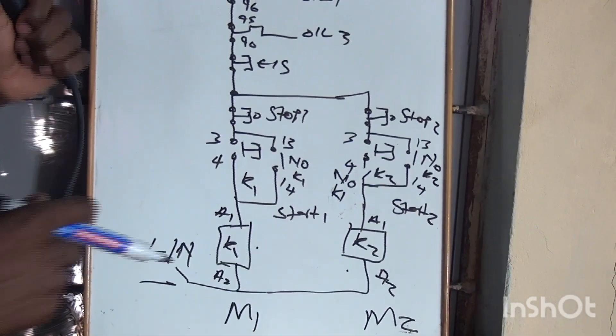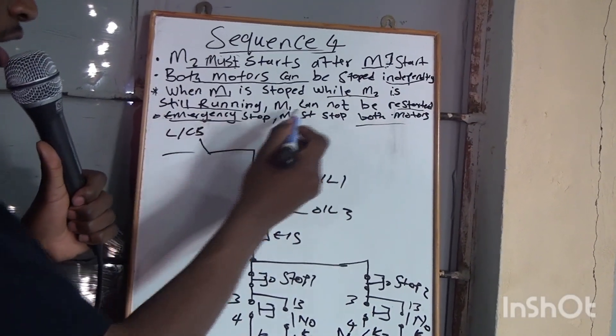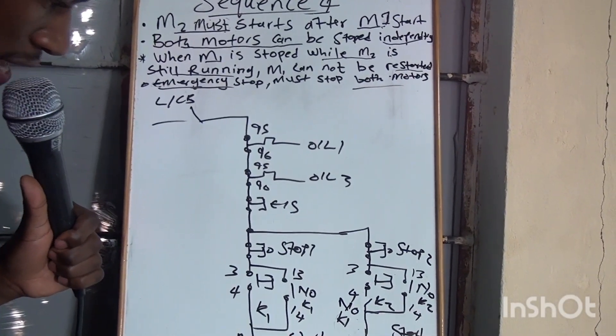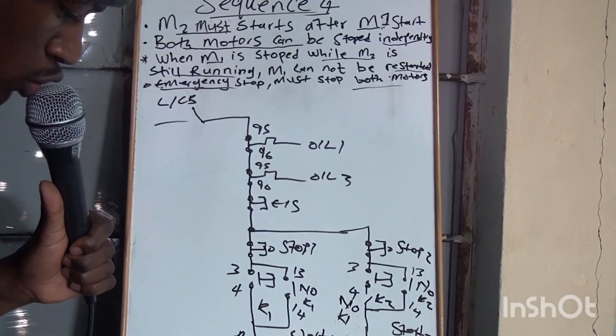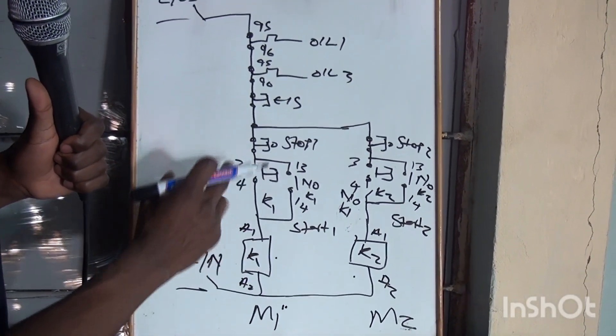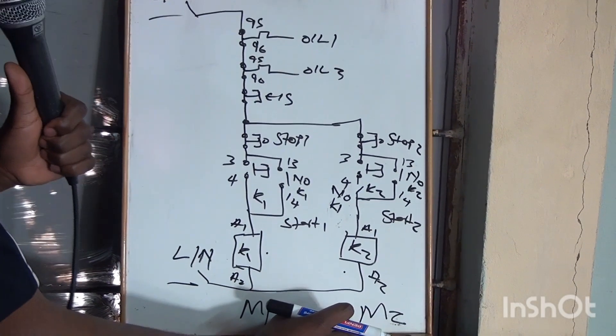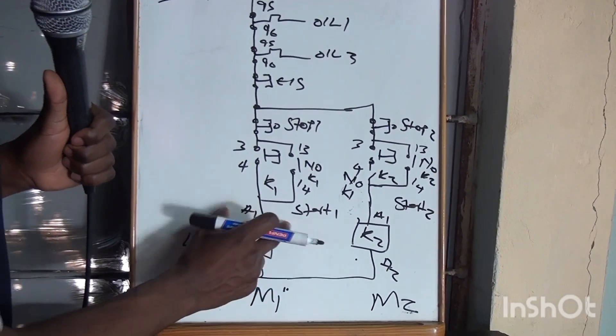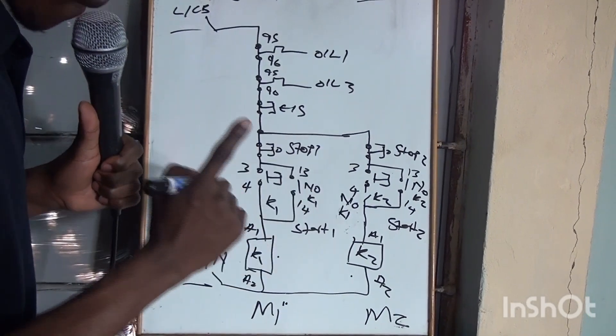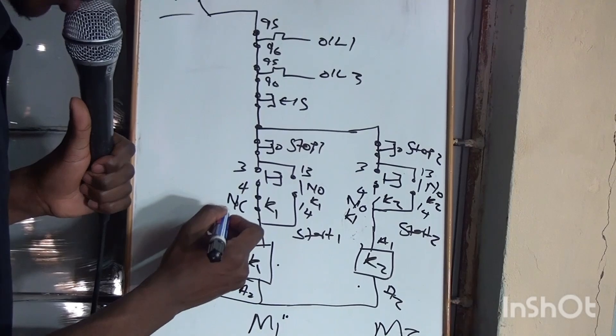Here's the third condition: when Motor 1 is stopped while Motor 2 is still running, Motor 1 cannot be restarted. So when both motors are running you must not be able to restart Motor 1 once you stop it. To achieve this, we are going to introduce a normally closed contact of K2 on the Motor 1 side.